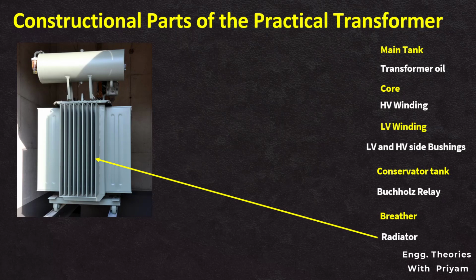Radiators are an essential component for the transformer as they help to dissipate the heat generated within the transformer core. This heat can cause the transformer to overheat and potentially damage it. The radiator is typically located on the outside of the transformer tank. It is made of a series of fins that increase the surface area for the heat transfer. Heated oil from the transformer circulates through the fins, releasing the heat to the surrounding air.